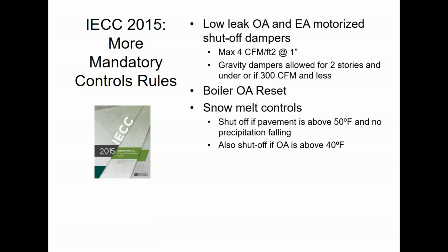But they have a little grid on top of them with a little electric wire on there. And if there's moisture on the grid, it completes the electric circuit and hence tells you that you have a wet sensor or not. You need a precipitation sensor. You also have to measure the pavement temperature. If it's above 50 degrees, you have to cut off the snow melt because that means it's not snowing. It means it's raining, right? If there's moisture and it's above 50, it's not snow or ice. And then you also have an outside air temperature cutoff at 40 degrees.